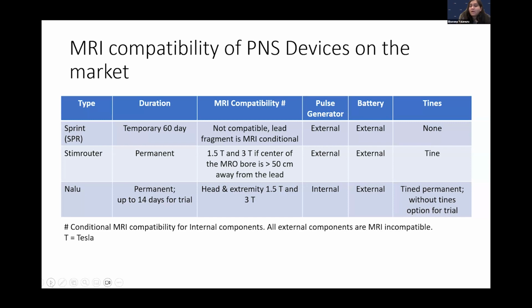Both the StimRouter and the Nalu leads are tined leads, which allow for the leads to anchor into the tissue and for fibrous tissue formation and scarring to occur to prevent displacement of the leads. And the MRI compatibility of all these devices is only for the internal components, not for the therapy disc in terms of Nalu, not for the external pulse generator transmitter in terms of StimRouter.